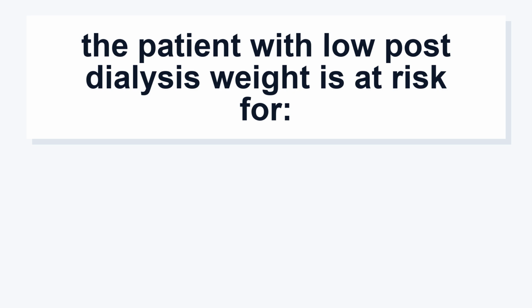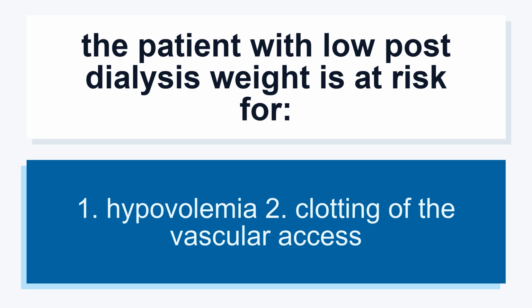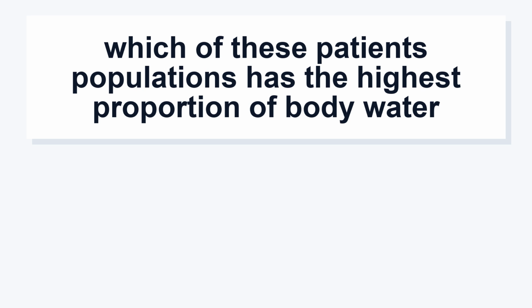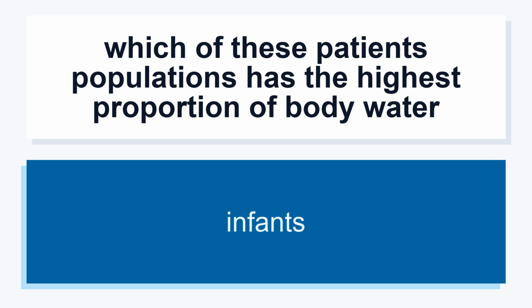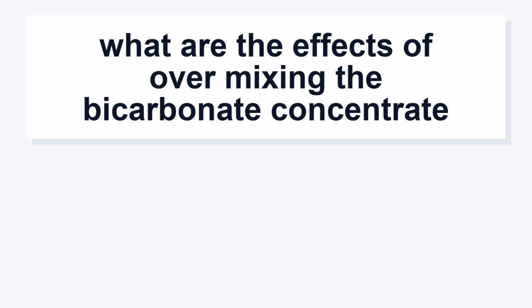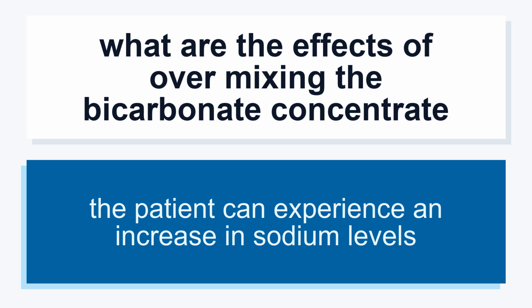The patient with low post-dialysis weight is at risk for 1. Hypovolemia. 2. Clotting of the vascular access. Which of these patient populations has the highest proportion of body water? Infants. What are the effects of overmixing the bicarbonate concentrate? The patient can experience an increase in sodium levels.